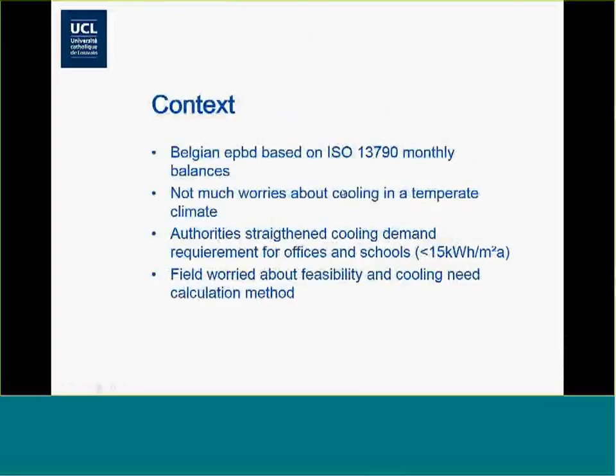Okay. So, as I said, I've been asked to say a few words about ventilative cooling in the Belgian method to calculate cooling loads, because this method is going to change in the coming months. In fact, we have a temperate climate, so cooling is not much of a problem here in Belgium compared with heating loads, for example. Until recently, when authorities decided to tighten cooling demands and more specifically set a maximum cooling need of 15 kilowatt-hours per square meter per year in offices and schools.